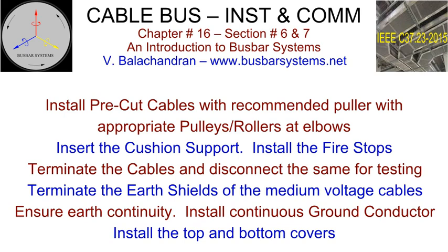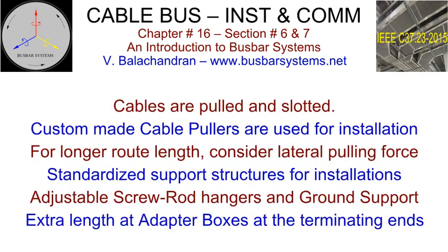Terminate the earth shields of the medium voltage cables as recommended. Ensure earth continuity of the cable bus. Earth the cable bus enclosure and the shield of the medium voltage cable as per the manufacturer's instructions. Install the continuous ground conductor along the side rail and connect to the station ground bus at least at either end. Install the top and bottom covers of the cable bus. Cables are pulled and slotted as per the drawings. Custom-made cable pullers are used for installation. For longer route length of cable bus, the lateral pulling force should also be taken into consideration.